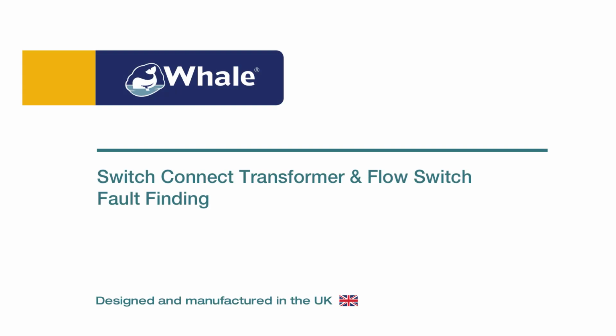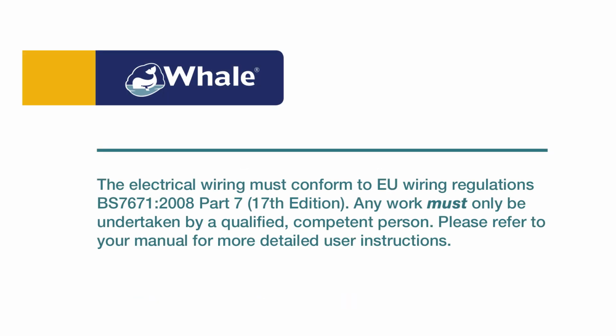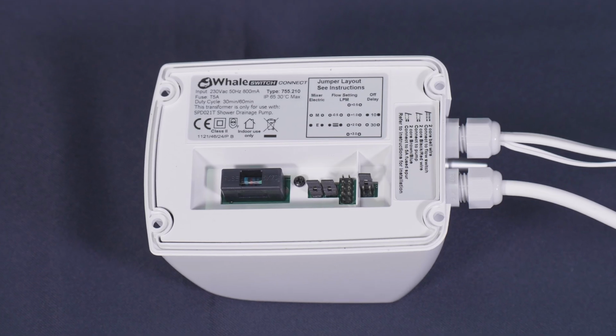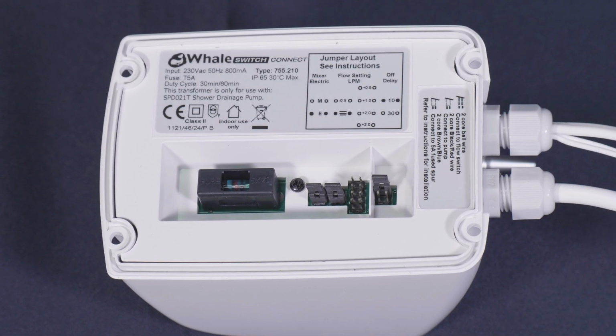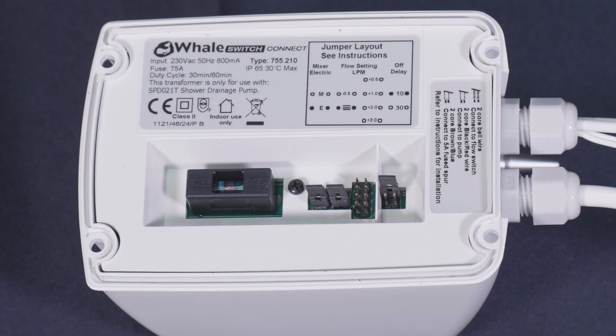In this video, you will learn about fault diagnosis when a pump does not start or does not stop running when using the switch connect transformer and flow switch. This refers to part numbers 755.210, 755.199, 755.120. You can check which transformer you have by looking at the label on the rear of the transformer. For example, the part number for the transformer shown is 755.210. The switch connect transformer can also be identified by the 2-core bell wire.